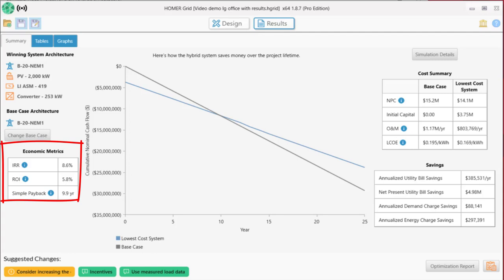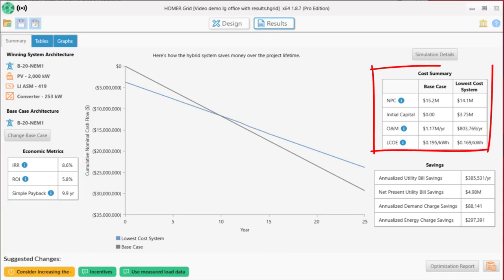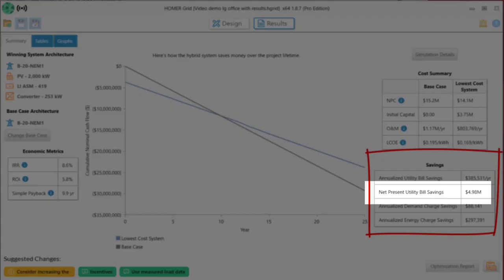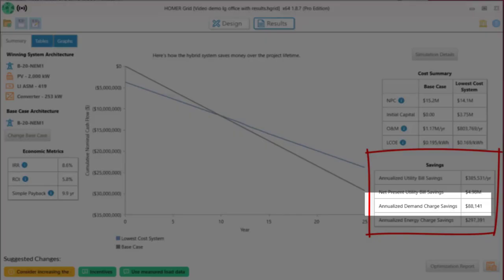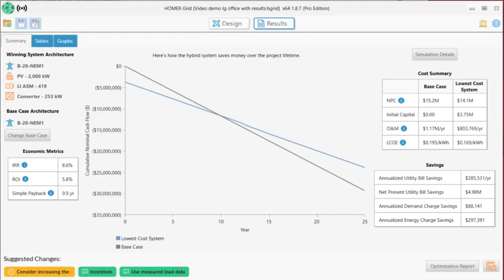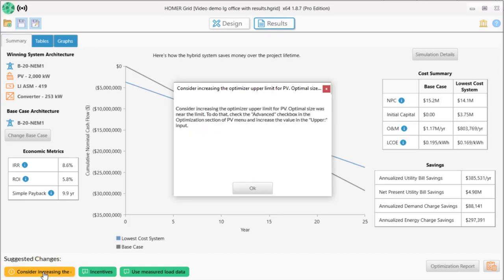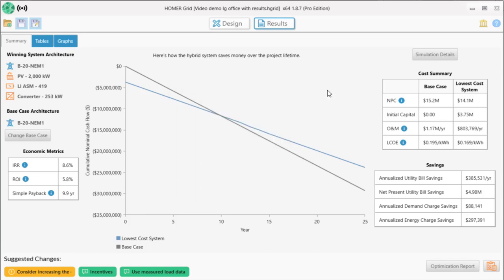This project has an internal rate of return of 8.6%, a 5.8% return on investment, and a simple payback of 10 years. To the right of the graph is a summary of costs for the two systems. The table below that summarizes the various savings, nearly $5 million total. Recall that reducing demand charges was one thing we were looking to do, and this project is saving $88,000 per year in demand charges, and this is all before adding any incentive programs, which can significantly increase ROI for many projects. Homer is showing a recommendation to increase the amount of PV. It will almost always do this because PV is so inexpensive that it makes sense to use as much as possible, but we already set the maximum based on the available space, so we will ignore this particular warning.